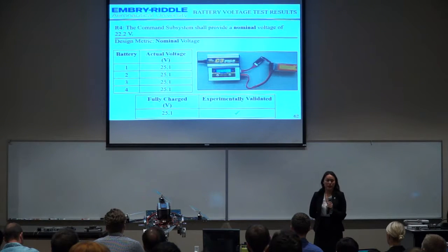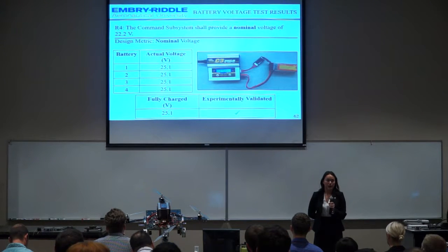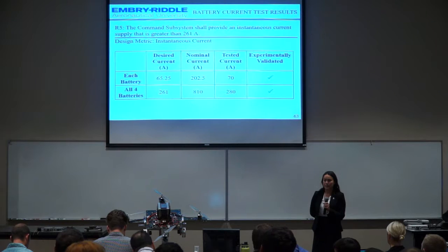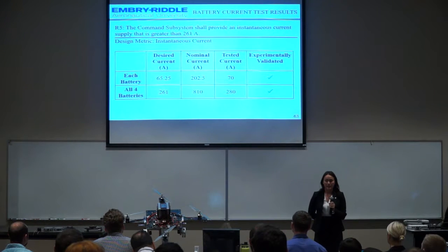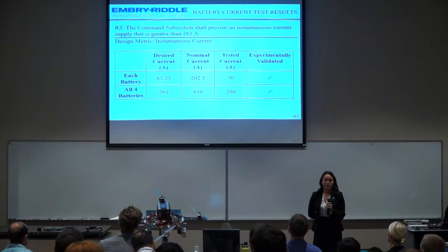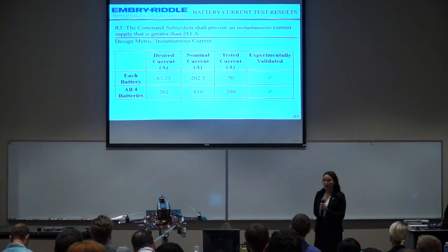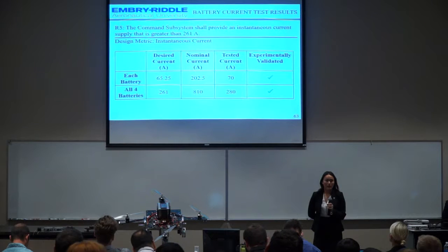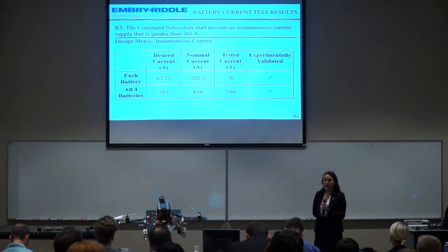The third test we conducted was a battery voltage test. This test validated our fourth subsystem requirement. This test was conducted for each battery. Each battery was balanced, charged, and then we measured the voltage across the battery using a voltmeter. Fully charged, each battery had a voltage of 25.1 volts, therefore validating this requirement. The fourth test we conducted was the battery current test. This test validated our fifth subsystem requirement. For this requirement, the desired current draw from each battery was 65.25 amps. We tested each battery to a current draw of 70 amps. Collectively, all 4 batteries produced a total current draw of 280 amps, therefore experimentally validating this requirement.